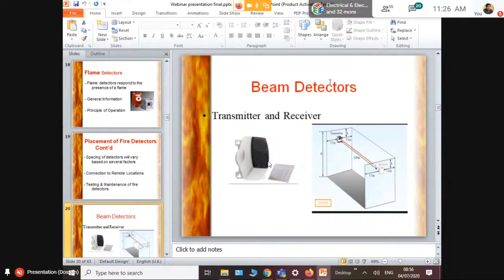Now, beam detectors. This is another type of detector, and it has to be installed in areas where we cannot install a smoke detector, or where the coverage of smoke detectors will not help. Sorry, this is how the beam detector looks. This is a transmitter, and this is a receiver. The transmitter will be wired up to the fire alarm system control panel.